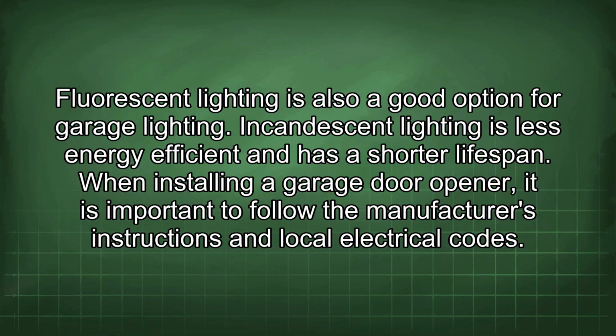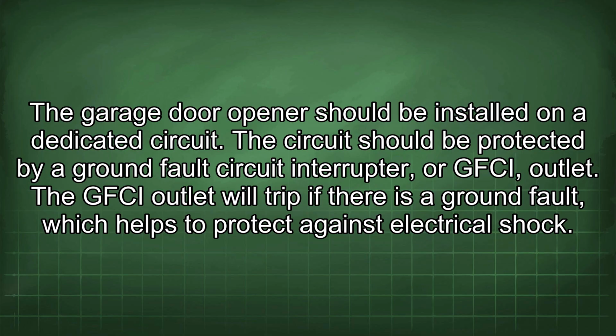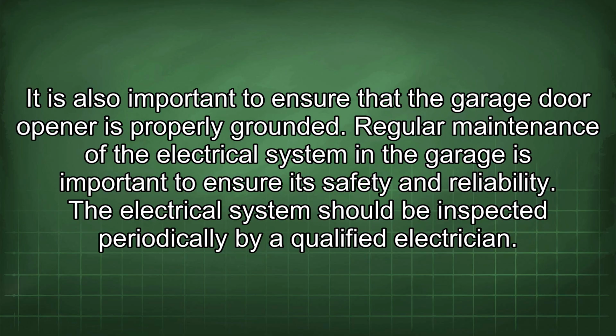When installing a garage door opener, it is important to follow the manufacturer's instructions and local electrical codes. The garage door opener should be installed on a dedicated circuit. The circuit should be protected by a ground fault circuit interrupter, or GFCI outlet. The GFCI outlet will trip if there is a ground fault, which helps to protect against electrical shock. It is also important to ensure that the garage door opener is properly grounded.